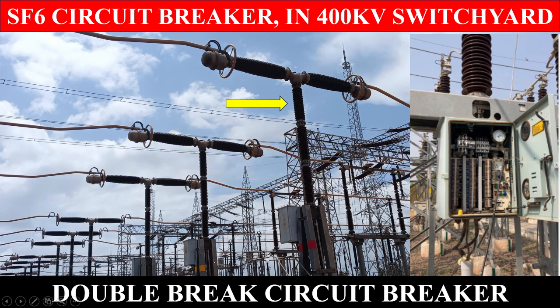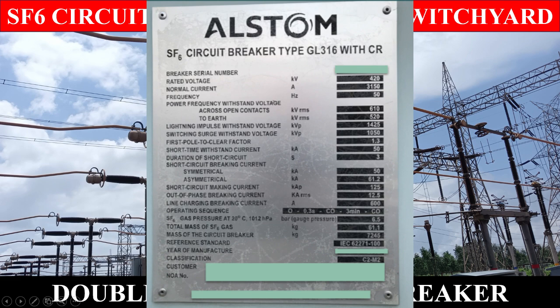The high-pressure flow of SF6 rapidly absorbs the free electrons in the arc path to form immobile negative ions, which are ineffective as charge carriers. The result is that the medium between the contacts quickly builds up high dielectric strength and causes the extinction of the arc. After the breaker operation, that is, after arc extinction, the valve is closed by the action of a set of springs.